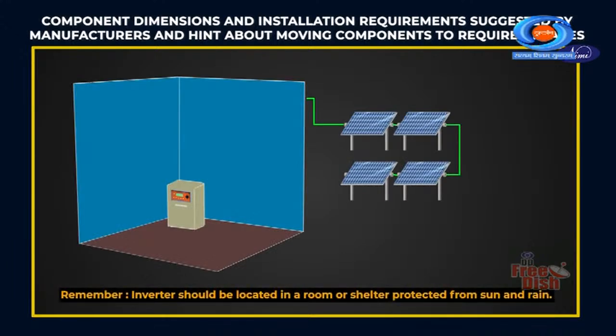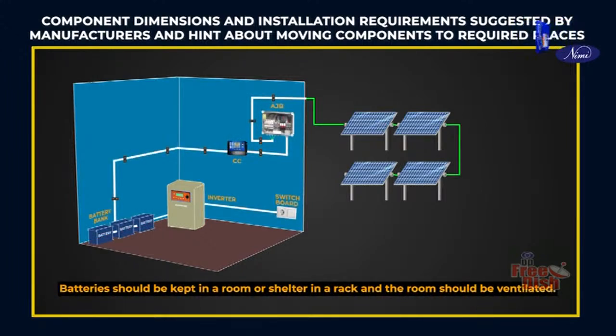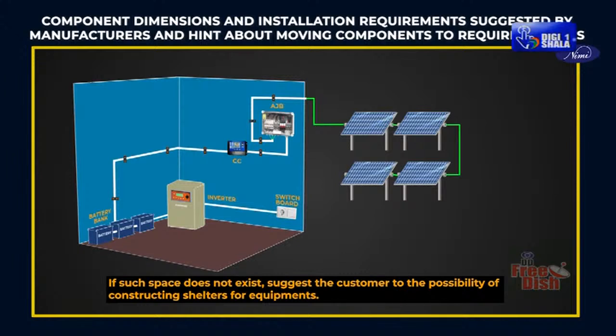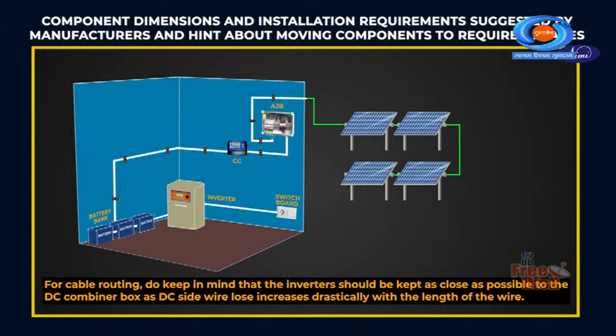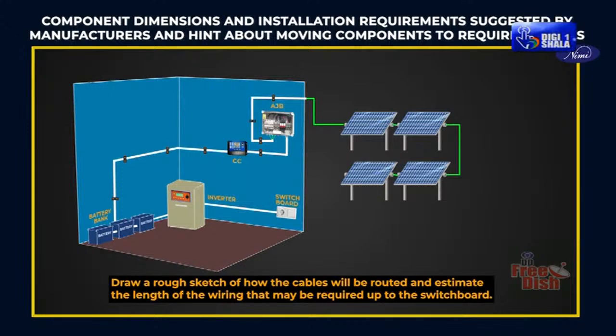Remember, the inverter should be located in a room or shelter protected from sun and rain. Batteries should be kept in a room or shelter in a rack, and the room should be ventilated. If such space does not exist, suggest to the customer the possibility of constructing shelters for the equipment. For cable routing, keep in mind that the inverter should be kept as close as possible to the DC combiner box, as DC side wire loss increases drastically with the length of the wire. Draw a rough sketch of how the cables will be routed and estimate the length of wiring that may be required up to the switchboard. Sketch out a drawing to show locations of all components on the site.